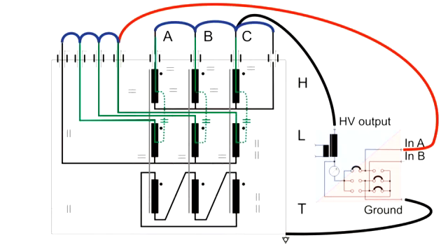If all bushings are connected to each other during a test, we only measure the dielectric losses. Now let's see what happens if we remove this connection. A capacitive current flows through the high voltage winding and the low voltage winding.